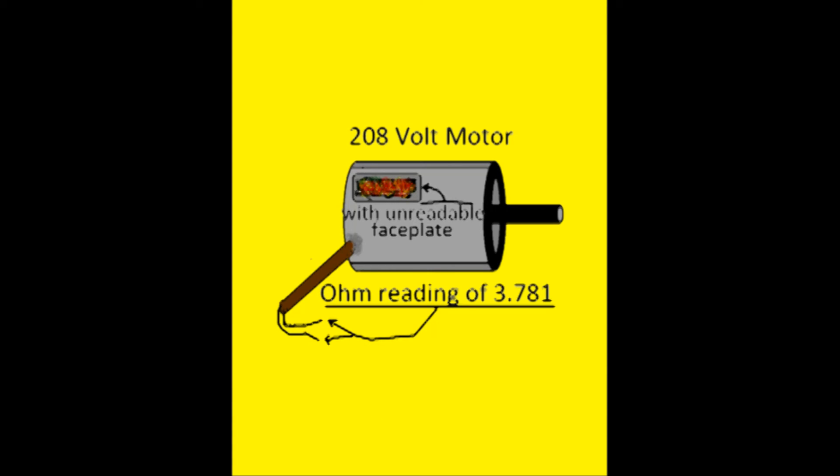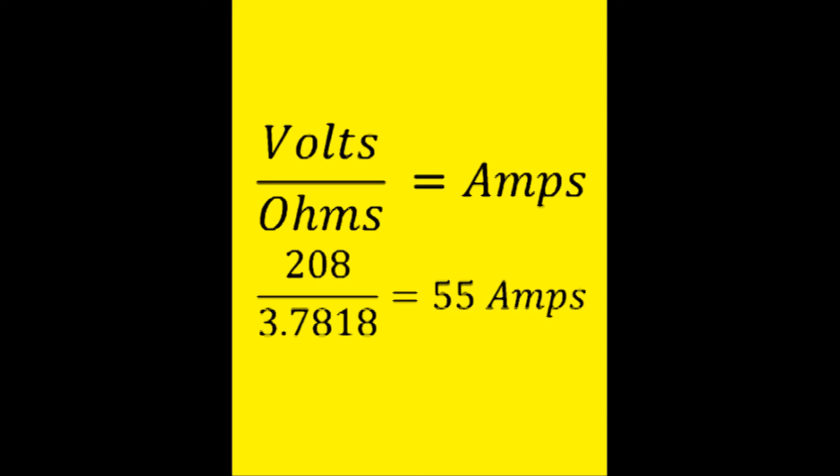Looking at the motor, you can test for ohms using the ends of the feed wires. So for now we're assuming that the voltage supply is 208 volts. You have 208 volts divided by 3.7818 ohms, which gives you a real-time amperage draw of 55 amps.